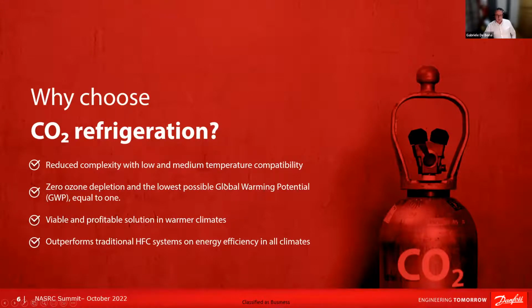Why choose CO2 as a refrigerant? Because it reduces the complexity with low and medium temperature compatibility. It has zero ozone depletion, and of course it has the lowest global warming potential, because it is equal to 1, which is the minimum you can have, and it has proven to be a viable solution for warmer climates too. In the past years, the development of the technology made this possible. We will see it, and it also performs with good efficiency in all climates compared to HFC and similar refrigerants.